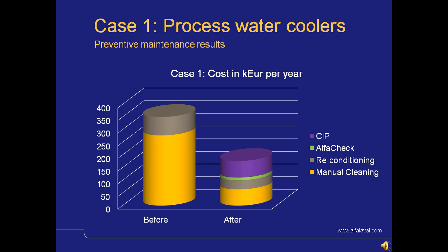So, what does this mean for the customer? The calculations done here are based on the cost of doing manual cleaning, i.e. labor, time of that, the reconditioning, i.e. refurbishment of the plates involving change of gaskets every 4 years before the optimization and every 8 years after the optimization, the cost of performing the AlfaCheck service, and also the chemical cleaning, the usage of chemicals, the equipment cost and the labor cost involved in there.